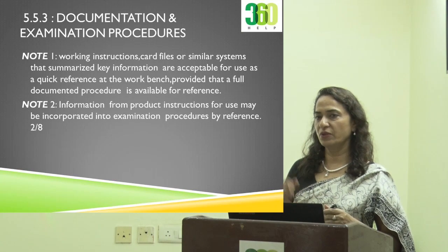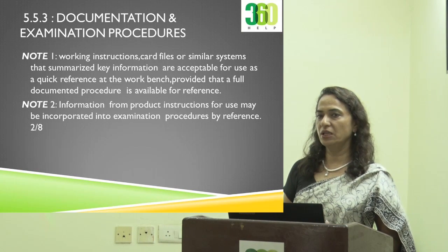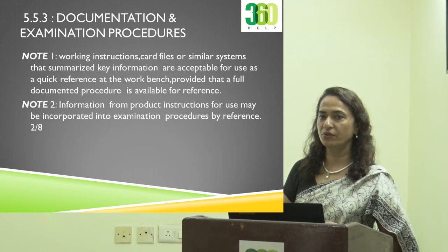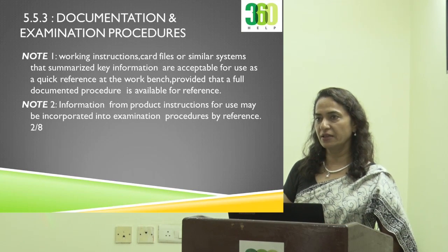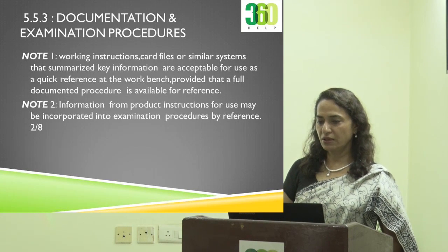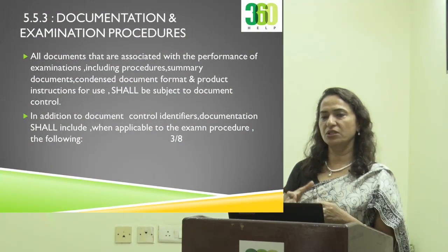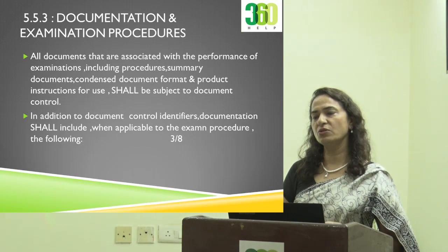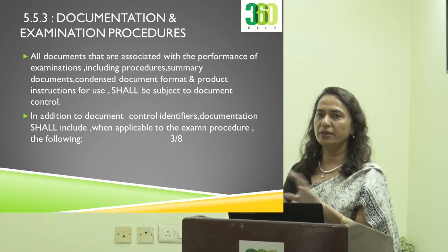Technical SOPs: for every test you have to write a procedure. Procedure in English, procedure in local language, because your technicians have to read it. If they don't understand English, you have to give it to them in their language. All the SOPs are what? Controlled documents. If you have small instructions out of your SOPs, some displays, then they will also be matching the SOPs and controlled. Nobody can change them.